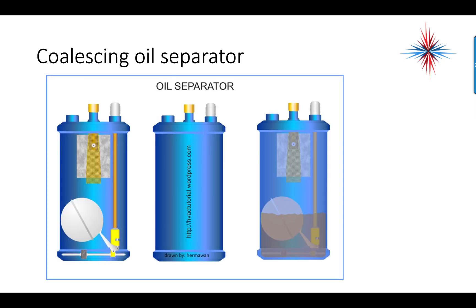Here is an example of a coalescing oil separator. The oil comes in, flows through a filter, and then drops down to the bottom. As the float switch rises, it opens the line back to the suction line or the low side of the system. The high pressure on the high side of the system forces that oil back to the low side.